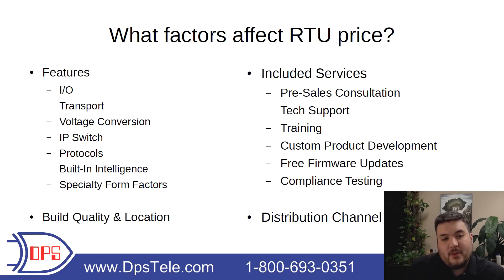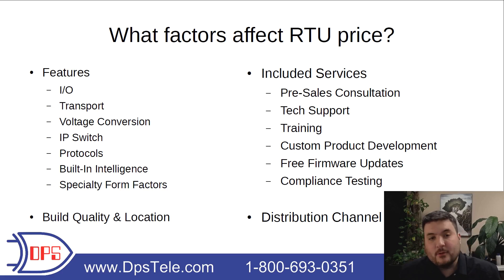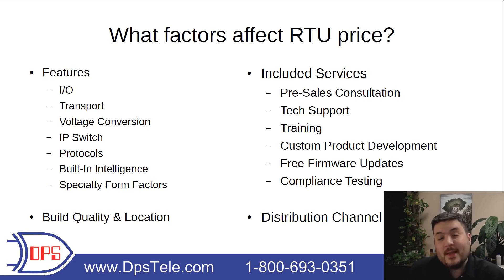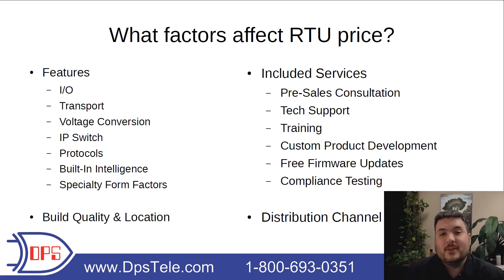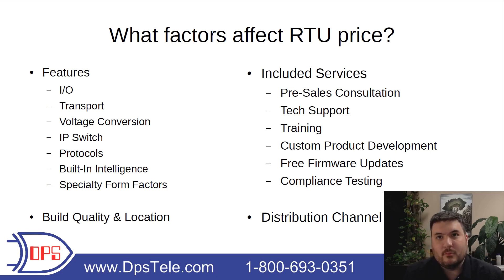Then there are value-adds. Voltage conversion is one example — you might have a negative 48-volt site and a negative 48-volt RTU, but a plus 12-volt sensor. Some RTUs will do voltage conversion internally and give you a power output so you can power that sensor. Some will also include an IP switch, so you can have a four-port or seven-port switch to give LAN to other devices at the site using the RTU's reliable, protected design, rather than putting a less reliable switch out there.